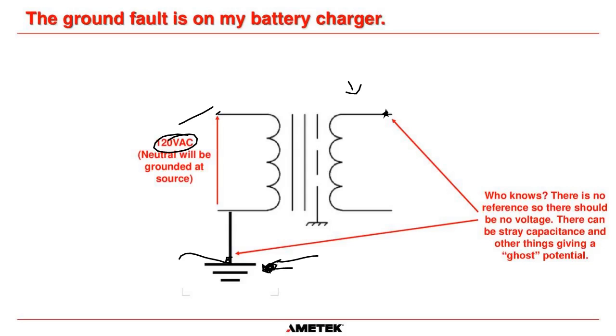There can be stray capacitance, just the way that cables are run and other things that give a ghost potential. But if you put any form of load on that, it would disappear quickly. It is just a ghost voltage. It's not actually a true voltage in this system. So you would not measure any voltage between hot and ground or neutral and ground on this system, because it has not been given a reference to ground. It doesn't know where ground is. Okay?